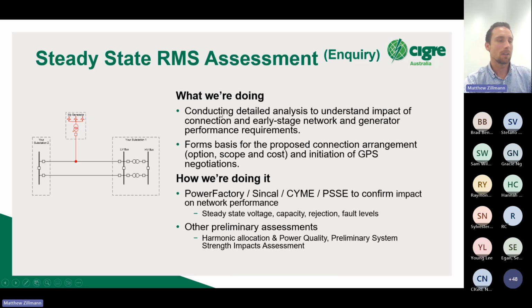So what we're actually doing, when you peel that back, is conducting detailed analysis to understand the impact of the connection on the network. That means looking at things like steady state voltage impact, impact on capacity and thermal rating, and rejection studies — what happens if this generator trips off, and what's the impact on the surrounding network. Another big one is fault studies: what's the impact on protection, what's the impact on fault rating of plant, and are we now starting to exceed that because we've embedded, or are looking to embed, a large generator in that area?